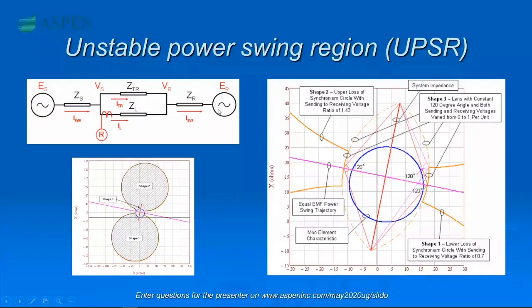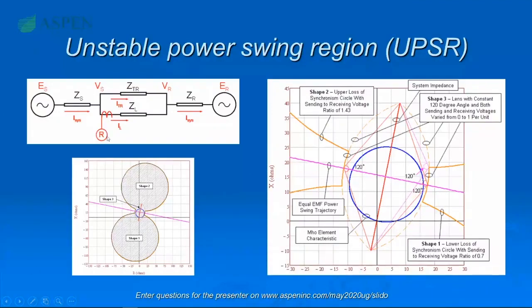Aspen one-liner is well equipped for you to make this calculation and do this plot. What we have in Aspen one-liner is not the simplified system, but a full model with thousands of buses, lines, and relays. The program can reduce that entire system to just a transmission line with two sources and a transfer impedance. If you have the line and relay already in the model, one-liner will help you show this graph and make the corresponding calculation.